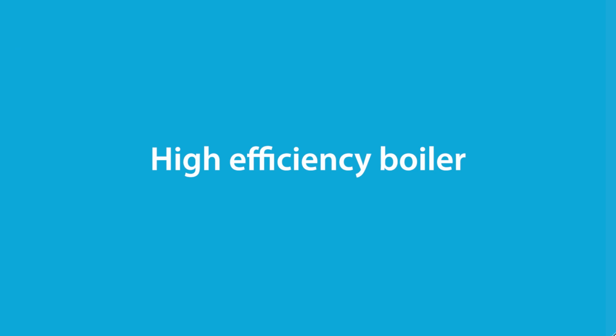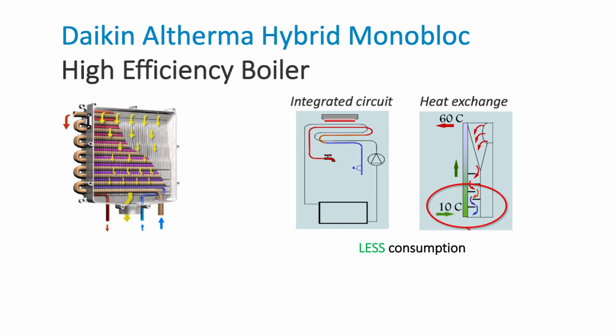The Daikin Altherma hybrid monobloc includes a high-efficiency combi boiler with a 2-in-1 heat exchanger integrated inside. Using the same heat exchanger for heating and hot water maximises efficiency during hot water operation, benefiting from a lower inlet temperature and maximising condensation of flue gases. The circulation pump is not required in hot water operation, and not having a 3-way valve and plate heat exchanger improves reliability. For the installer, a reliable system is one they can fit with confidence. For the property owner, they benefit from the best efficiency possible.